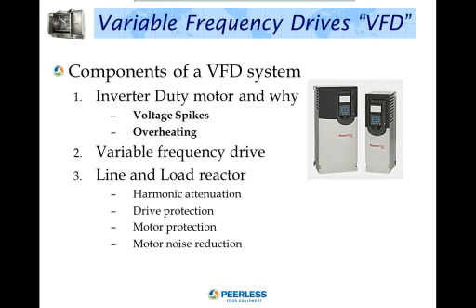Line reactors. A line reactor can protect motors and reduce power line distortions from VFDs. A line reactor acts not only as a current limiting device, but it also filters the waveform and attenuates electrical noise and transients associated with the system. You can install reactors in mixers, rotary dough feeders, sandwich machines, and many other types of equipment to extend the service life of the VFD and motor.